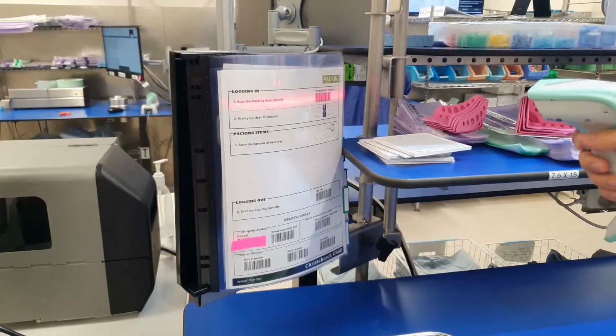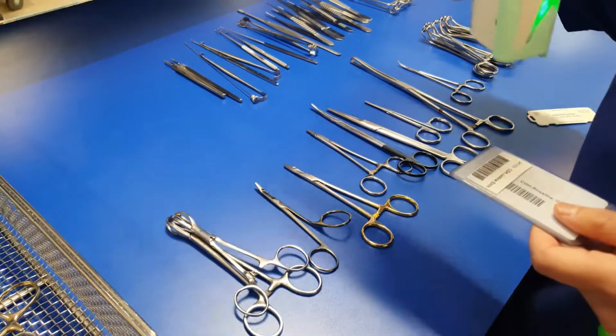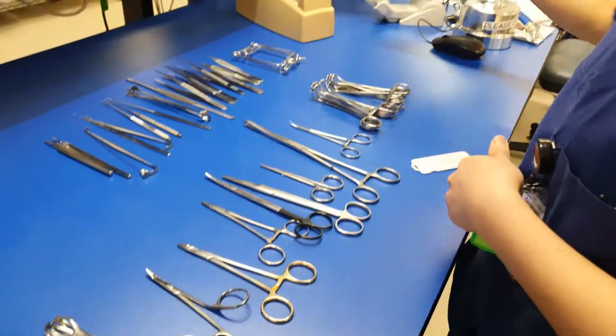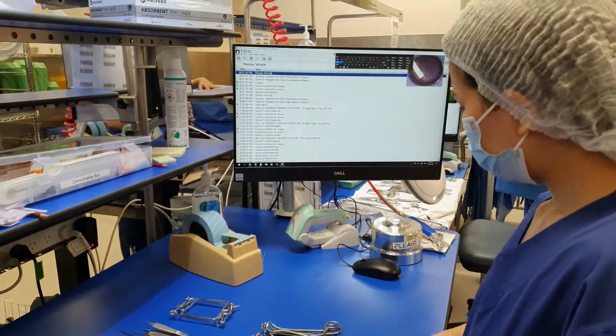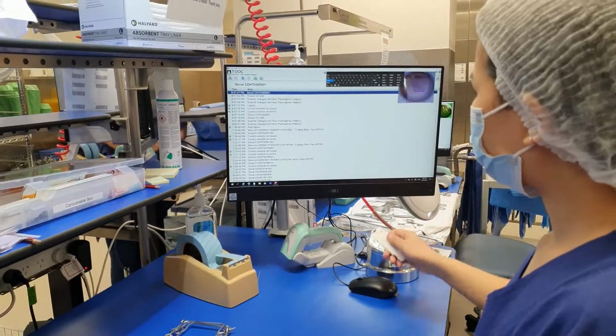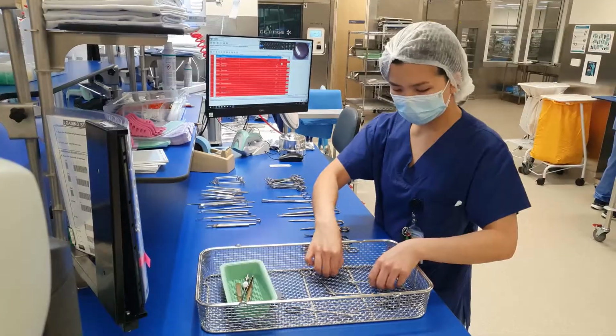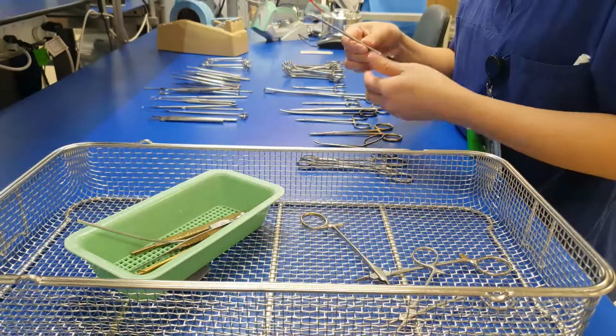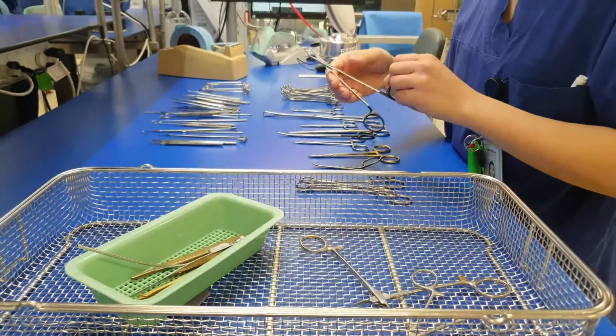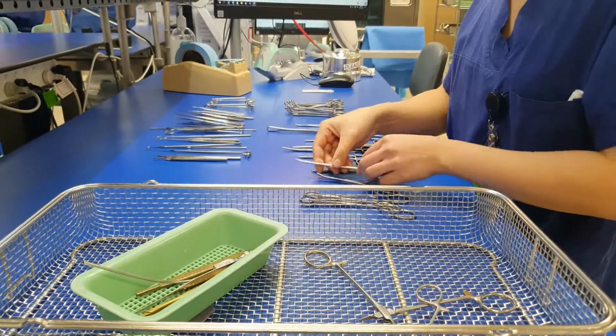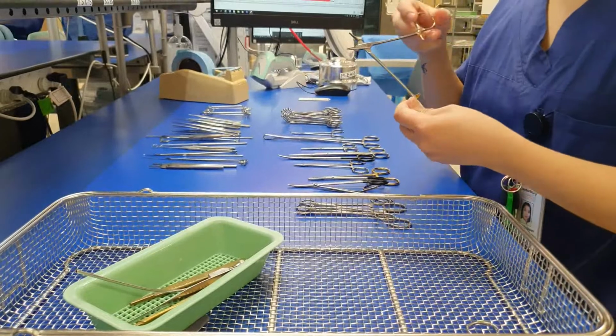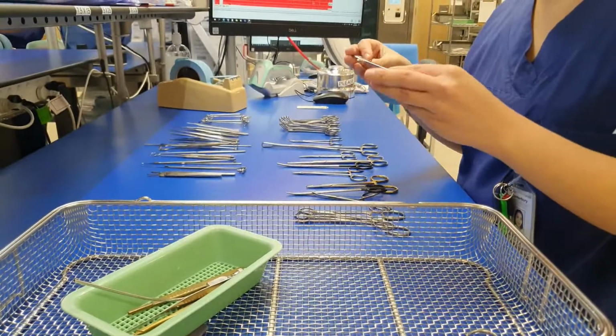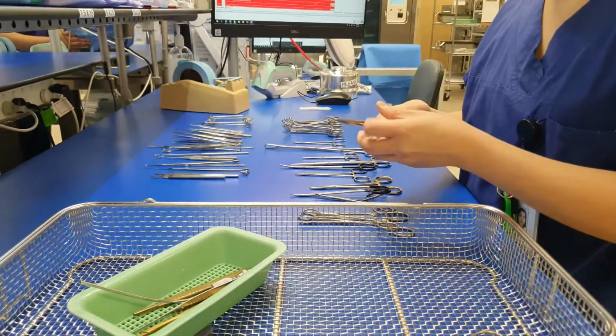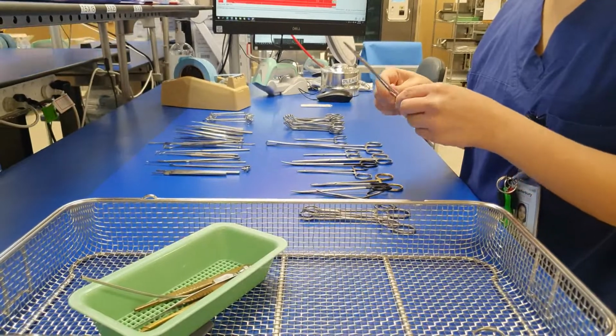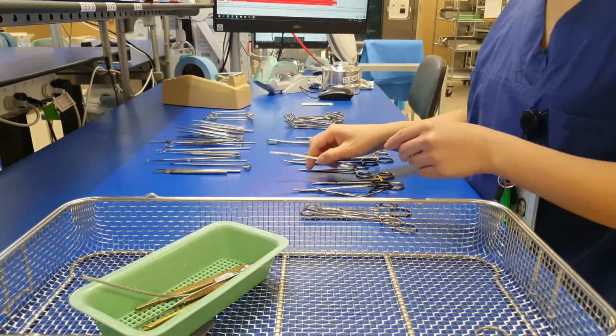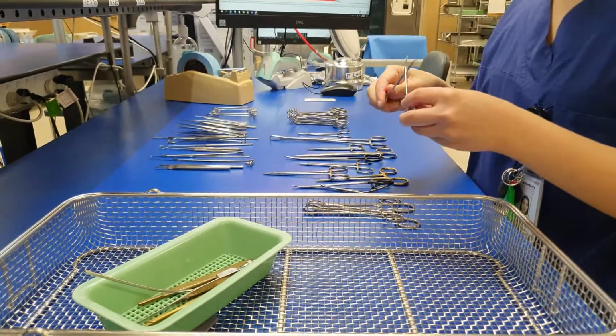Today, we are doing a plastic set. We start by scanning the TDOC system to access whichever set we are doing. When inspecting, we make sure instruments are fit for their purpose, that they would not cause harm to the patient or end user, and that they are used as intended. We make sure that every reusable medical device is inspected and clean, meaning all surfaces are free of contamination.